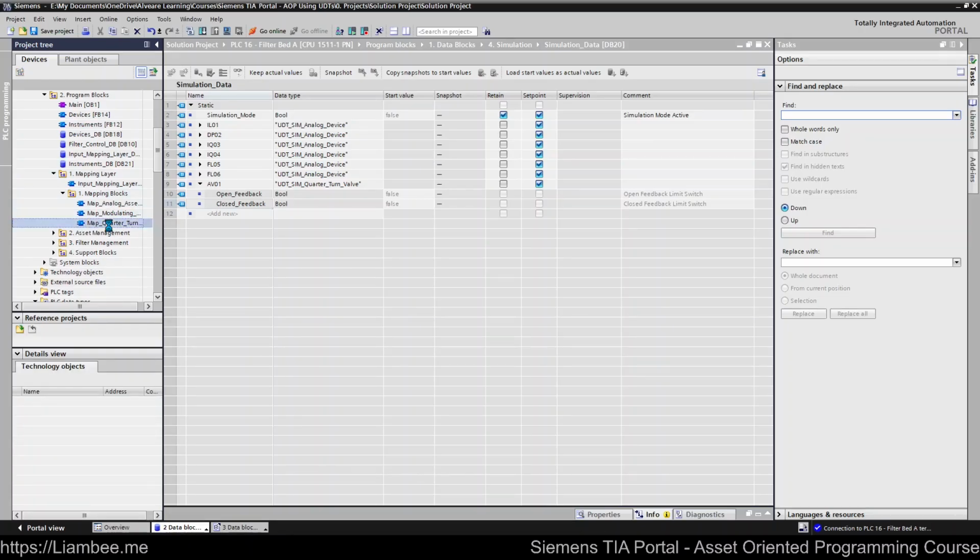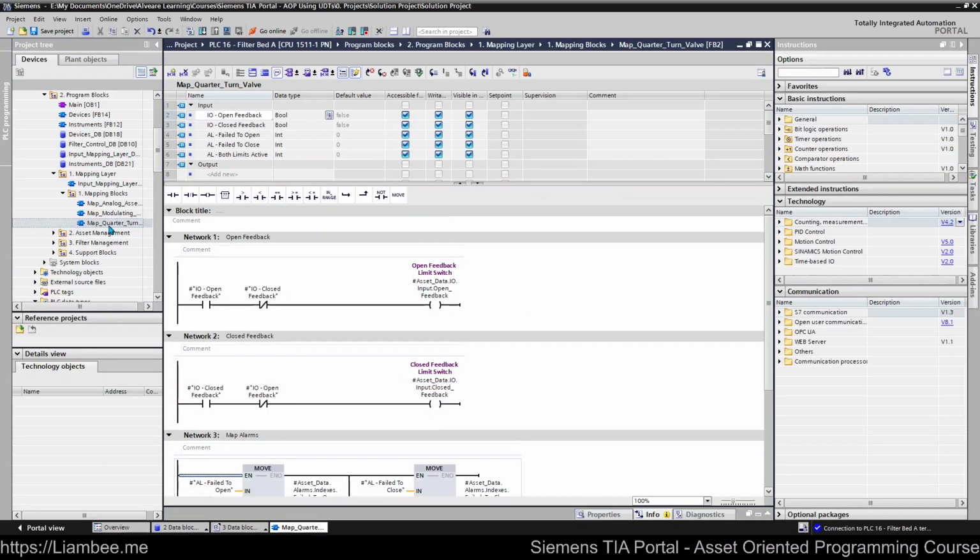Always a good idea to create these as function blocks, even if right now you don't need it to be a function block. If you ever want to add a timer or anything like that in, and you've made it as a function, it just becomes a bit of a faff to swap it over. I prefer to just create function blocks for them. It's not really doing any harm, and you just create it as an instance in the mapping layer, and then it's nice and easy to work with.